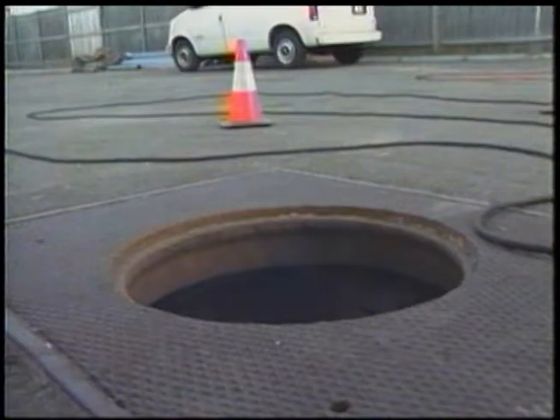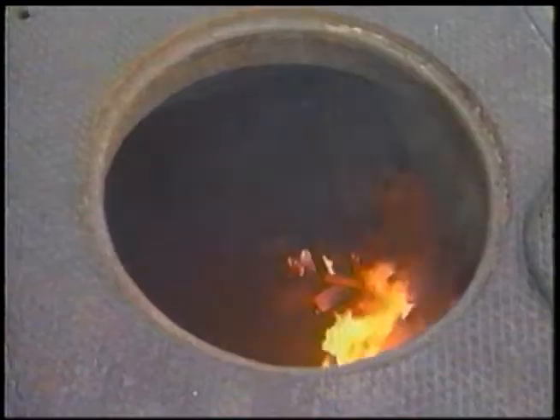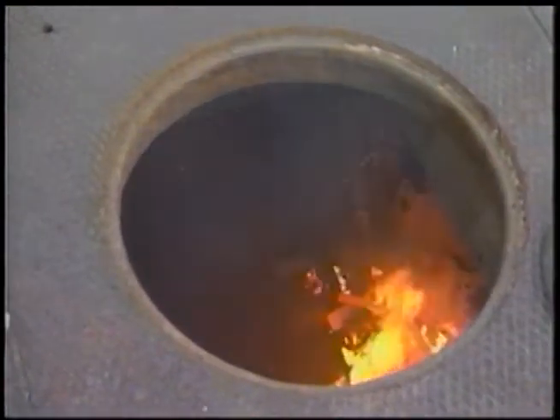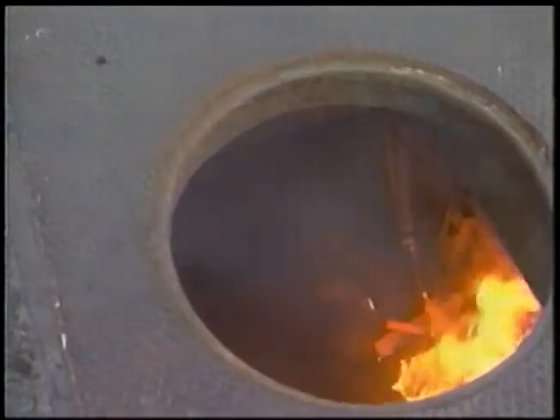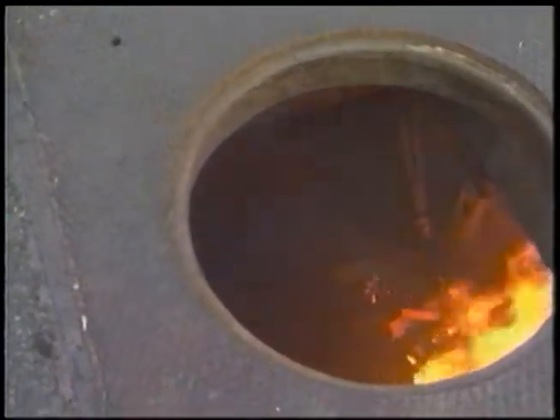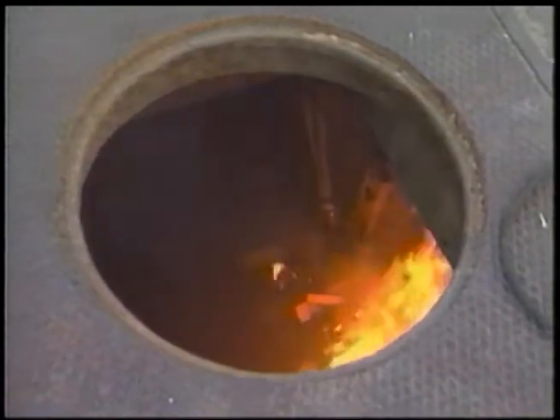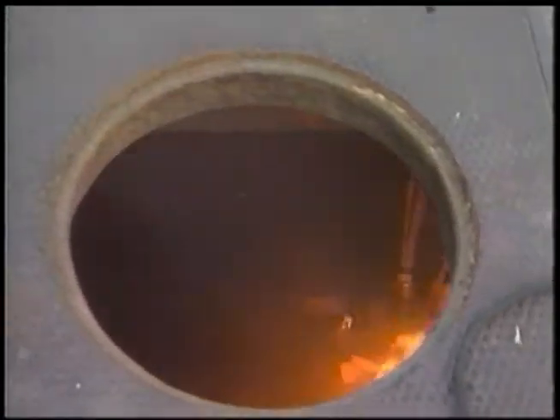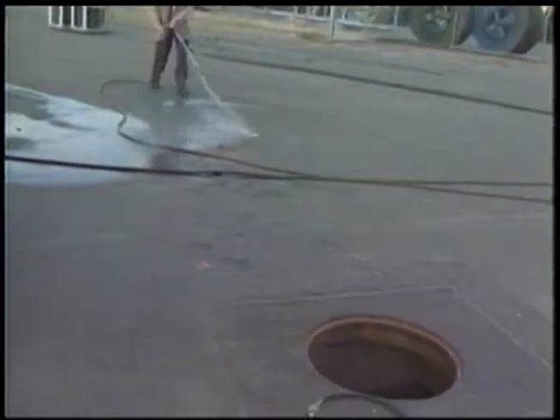You can see the fault and that it is slowly beginning to set the debris on fire. When I begin to put the fire out, I will not stand directly over the manhole. Instead, I will approach it from a distance and spray the ground ahead of me as I get close to the manhole. I'll spray inside the manhole as I get closer to the opening. You should never stand directly over an open manhole that's on fire or smoking, in case there is a sudden explosion.